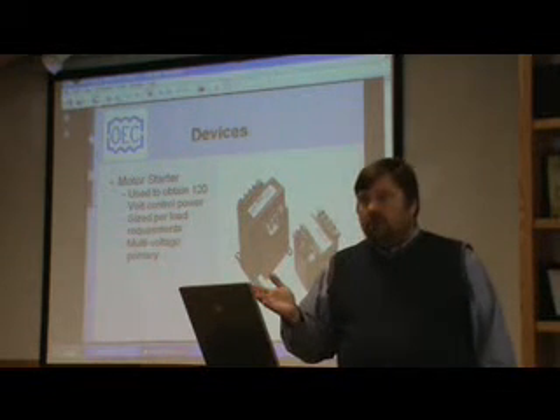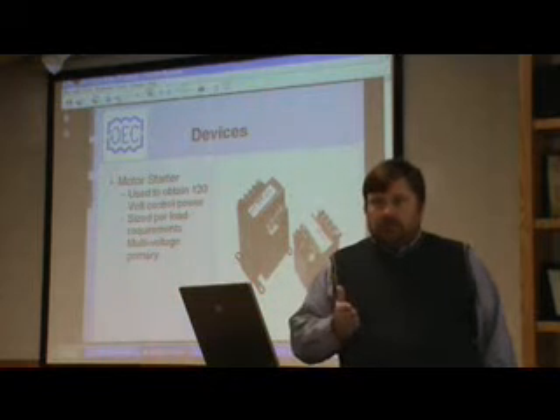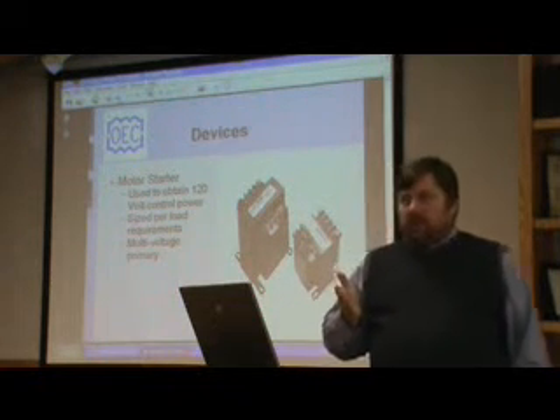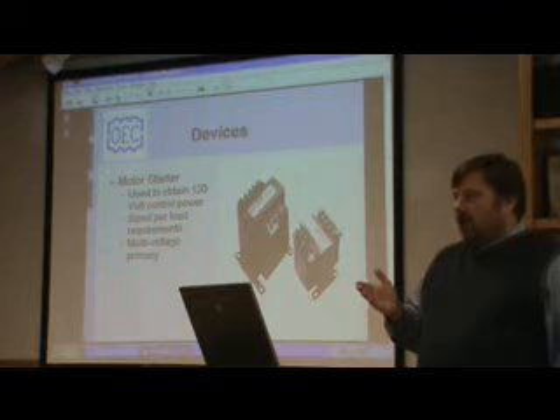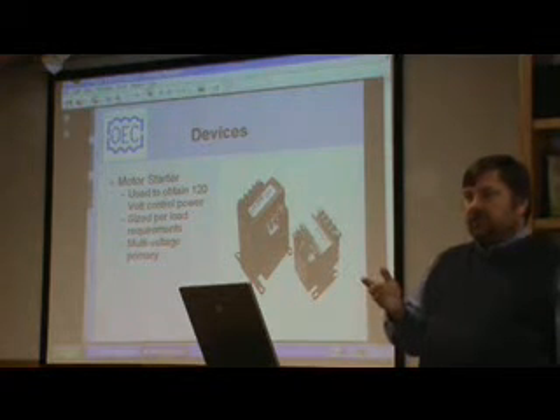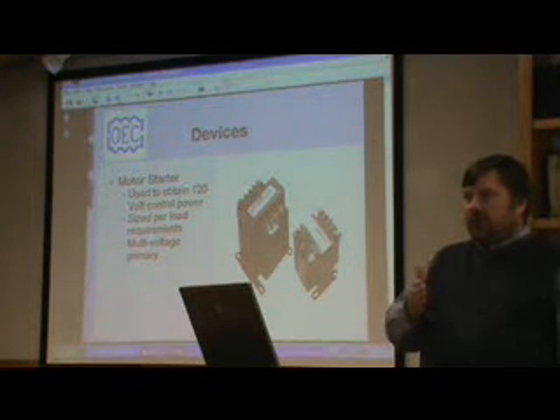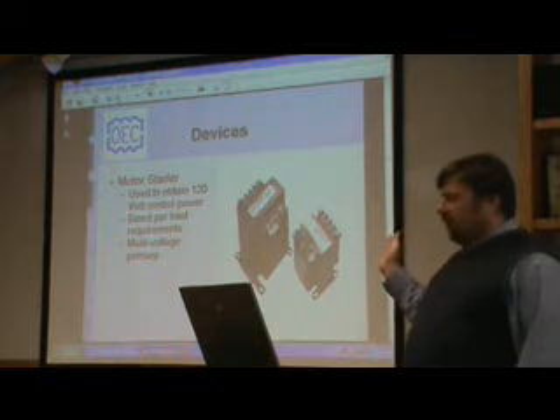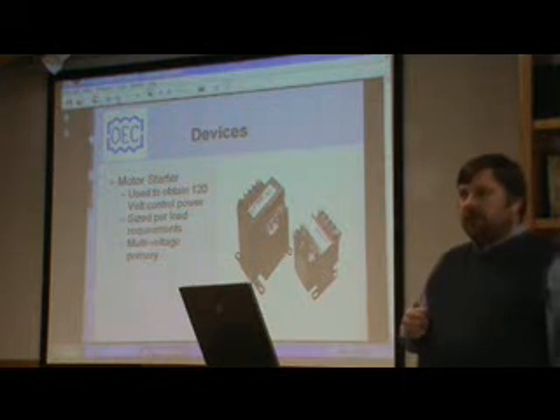It's sized per the load requirements. The control section is going to take a certain amount of amperage to run. A lot of specs we'll see call out to have a GFCI receptacle. So if those devices are included in the panel, we have to make sure that transformer is sized large enough that it will handle the load for those devices.